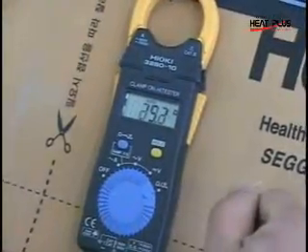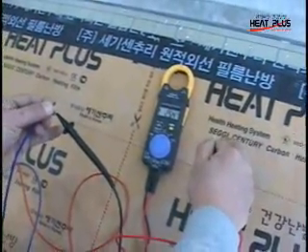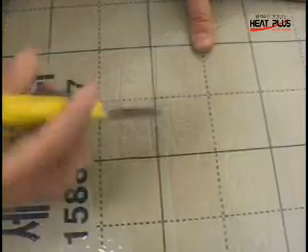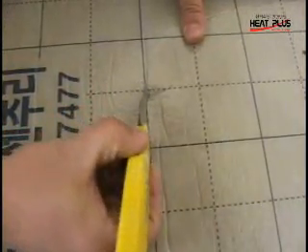Thereafter, the total resistance value of the lines connected in serial has to be measured to calculate the total consumption power. At this time, the maximum capacity for each adjuster is 4 kilowatts, but it shall not exceed 15 meters with the width of 1 meter.